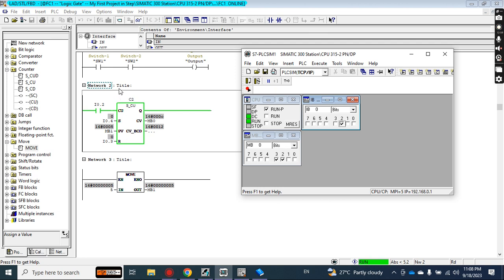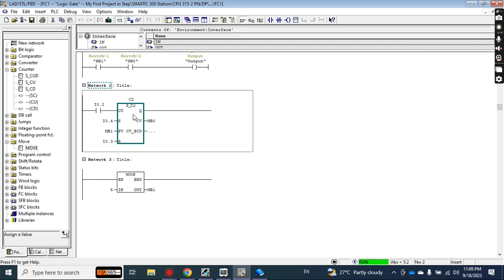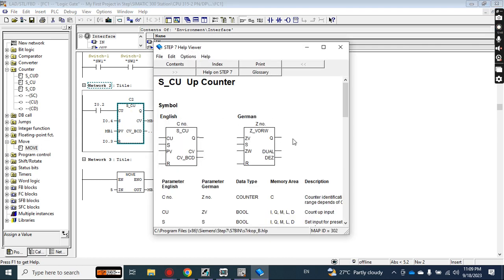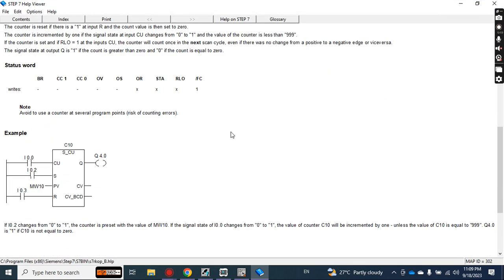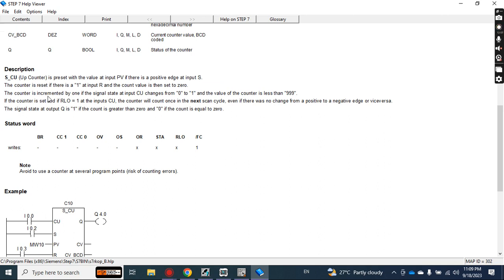These are the key points about the up counter. In this video you learned how to use the counter, how to initialize it, and how to reset it — these are the basic inputs of the up counter for any programming logic. If you want more details, right-click the counter block and press F1 to get help. The counter increments by one when the signal at input CU changes from 0 to 1, and the maximum count value is 999.